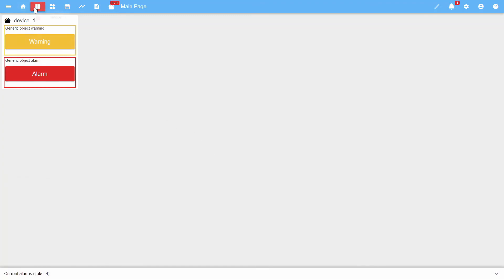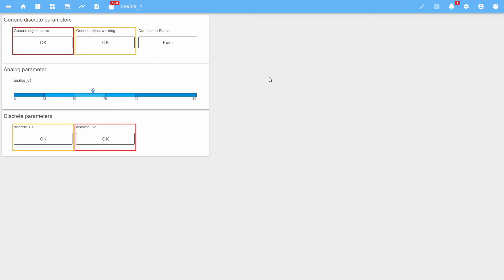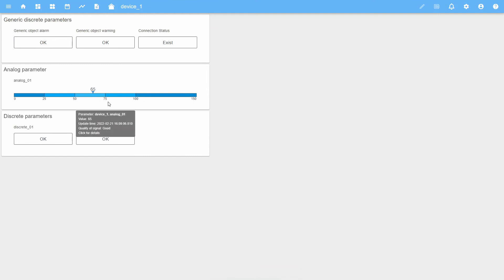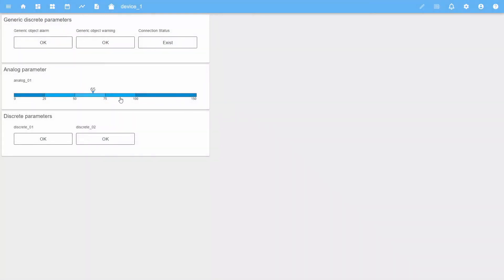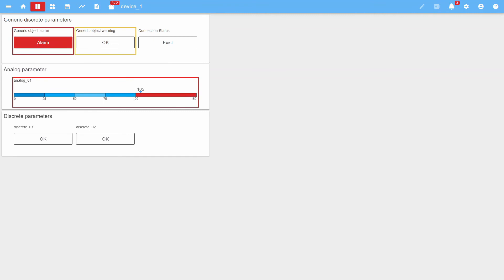Let's get back to the object page and consider alerts for analog parameters. Up to four alerts can be generated for an analog parameter — two alarms and two warnings. The set limits can be seen directly on the widget for parameter analog_01. You can change these limits by clicking on this widget. Let's simulate the exit of the parameter value beyond the limits — first beyond the warning limit and then beyond the alarm limit.